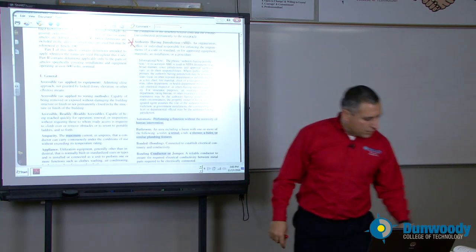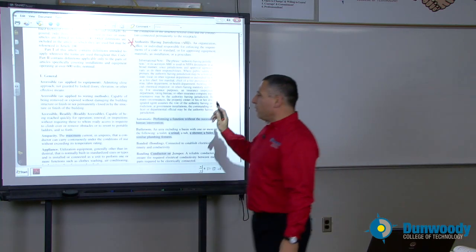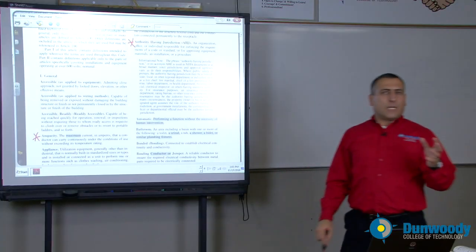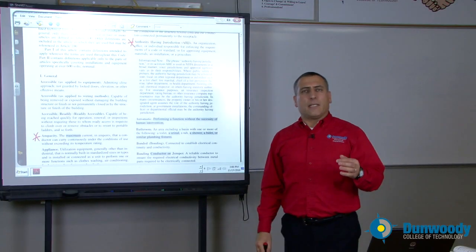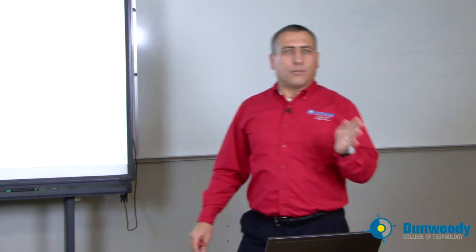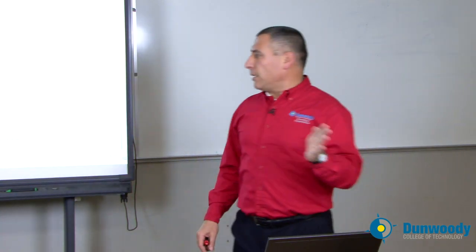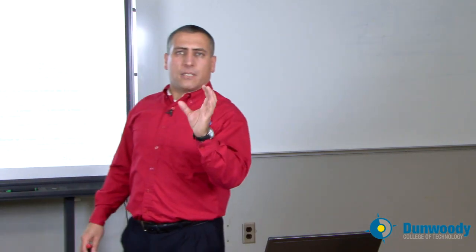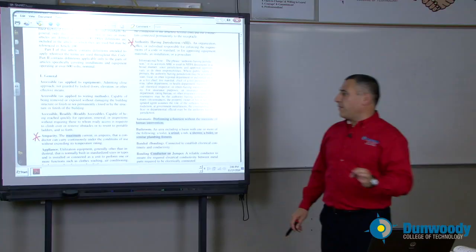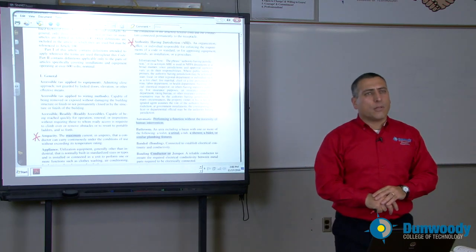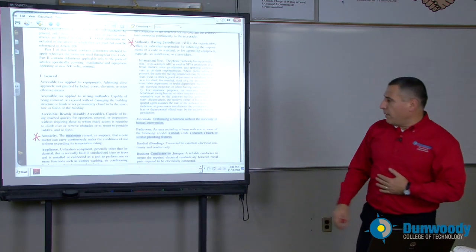Who is the authority having jurisdiction? Another term — the ampacity. When I say number 14 conductor, number 14 conductor cannot carry more than 15 amps. That's the amount of amps that the conductor can carry under certain conditions, normal conditions. When I say this conductor can carry only 23 amps, this means I cannot exceed that 23 amps. Very important — the ampacity: how much current you can push through a copper or aluminum conductor. Extremely important.